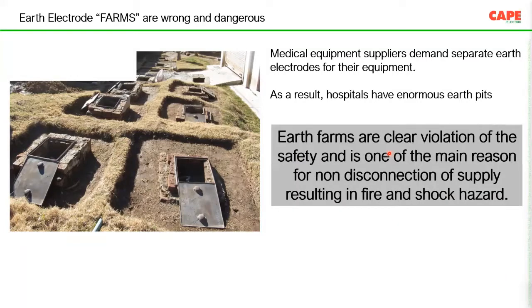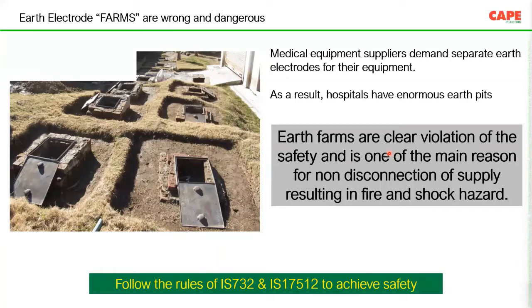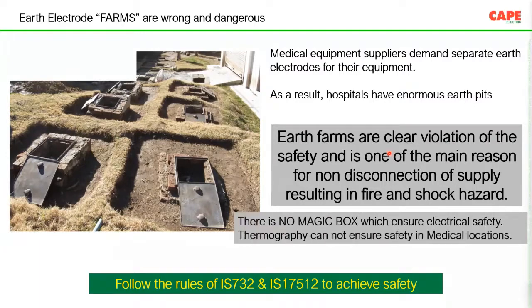So earth farms are a clear violation of safety, and are one of the main reasons for non-disconnection of supply, resulting in fire and shock hazard. Please don't make them. What you should do is clearly follow the rules of IS 732 and IS 17512 to achieve safety. Also, don't believe in magic boxes. There is no magic box which can ensure electrical safety.